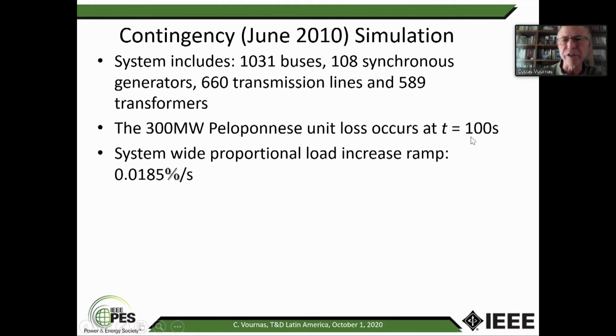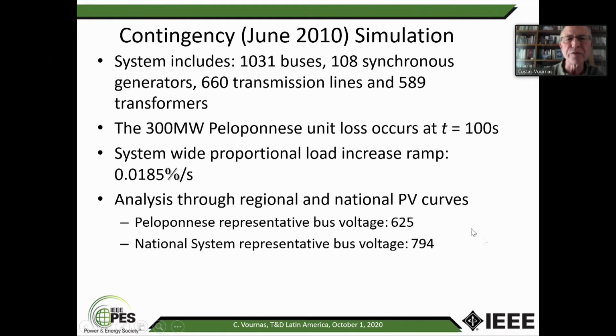So we have the contingency occurring at 100 seconds of simulation time. And then we follow with load increase, but this is not load, this is load demand. It does not mean that the load will cover this demand, because if voltage drops, the load is voltage sensitive. It has a sensitivity of around 1.5, which means it is something between constant current and constant admittance, but it is changing with voltage. So this ramp here is of load demand, not load consumption. And as I said, we'll do the analysis with the regional and national PV curves.